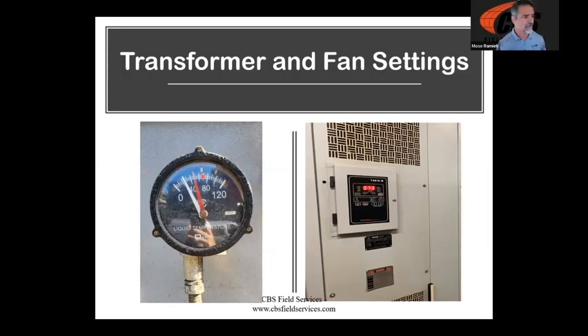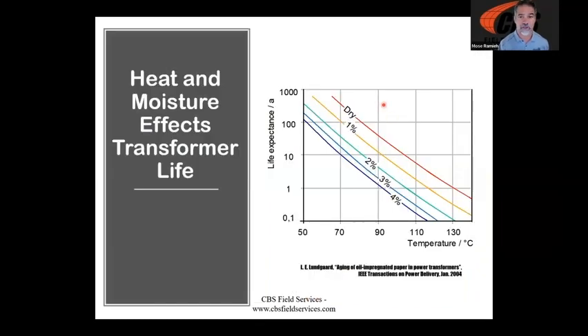It's interesting to point out that this little orange dot right here is the first step for the fans. As the temperature comes up, this white needle will get to this little switch that hides behind the gauge, and it's going to start the fans. You'll note that that's set at, what is that, 60, 65 degrees C. That's not a high temperature, but as I'll point out on the next slide, it is going to shorten the life of our transformer.